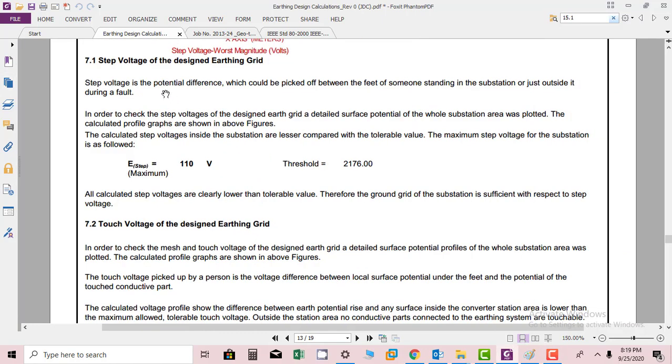Hi friends, in this section we will go through step voltage of the designed earthing grid. Step voltage is a potential difference which could be picked off between the feet of someone standing in a substation or just outside it during a fault.